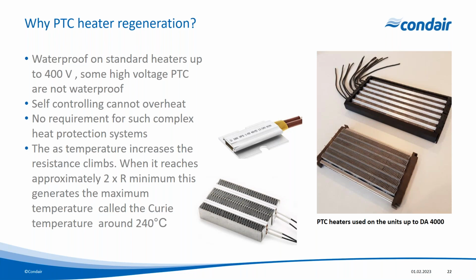Some PTC heaters are not waterproof. All the ones that are on our units for these low temperature applications are waterproof, just in case there is any condensation in there. Well, the benefit of a PTC heater is that it's self-controlling. It can't overheat. So you don't have the requirement for really complex heat protection systems.